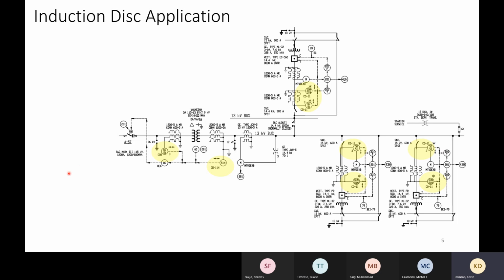So here's a pretty simple one line. It's coming off a 115 kV source. We come here, 20 MVA transformer. Since it's a one line, it shows that there are 3 CO9 relays doing 50-51 elements here. On the low side of the transformer, there's a single neutral, so 51N. It happens to be a CO11. Both of them, if they operate, they get the 86 relay that then goes and opens the circuit switcher.